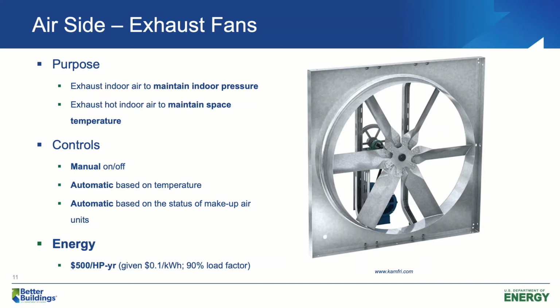Here we have a number of $500 per horsepower per year. This number means that the annual energy cost for a 1 horsepower motor with 90% load factor and 10 cents per kWh electricity price is about $500. That means if we can reduce the operating hours by 10%, we can save $50 a year. This number is very handy when you are trying to estimate the energy savings from reducing operating hours of motors.